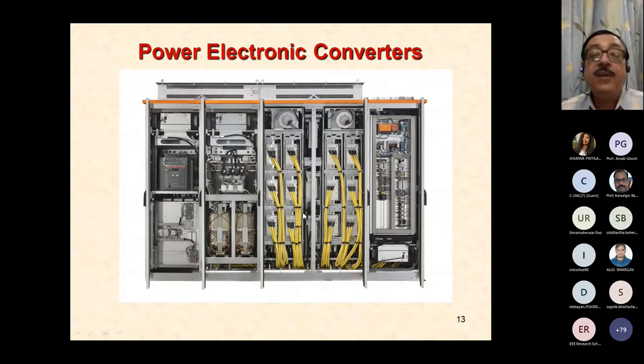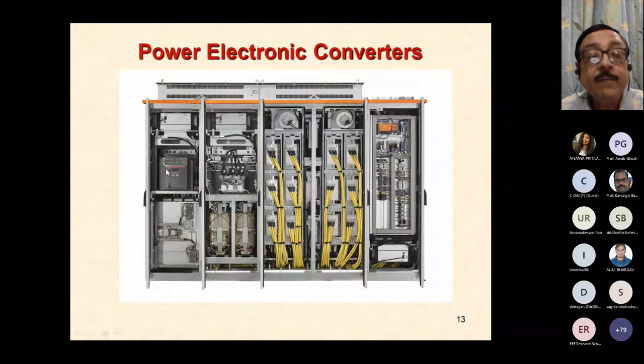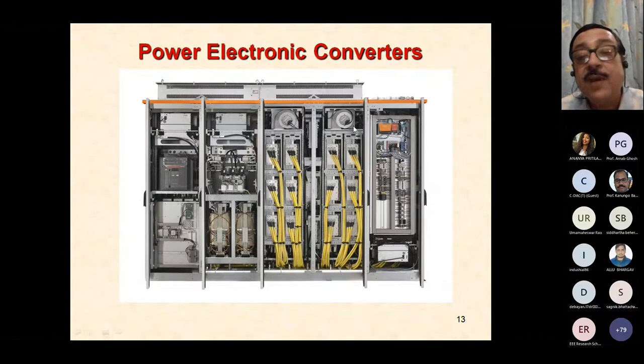This is a typical power electronic converter, not the small converter that we have in the lab, but what we put out on the network in terms of distributed generation. And this converter has many things built into it. You can see large switchgear, magnetic components. Then you have the semiconductor stack. The semiconductor stack has cooling fans on the top, control circuits, etc. So everything goes into building a tall rack like this. And you can have several such units stacked side by side. These are filters for the air to flow out. Nothing should be able to enter.